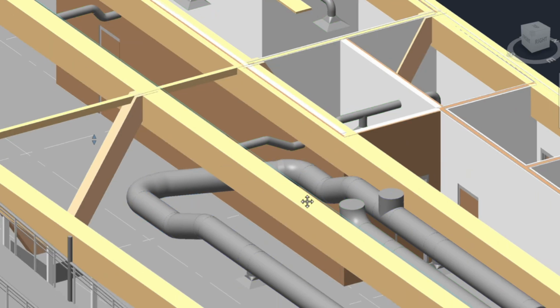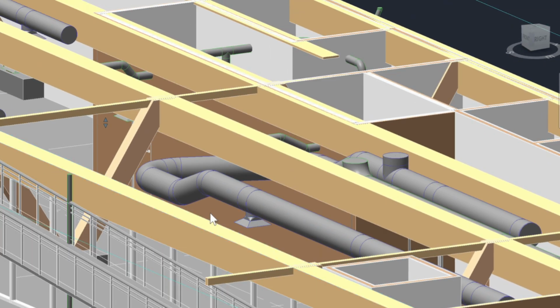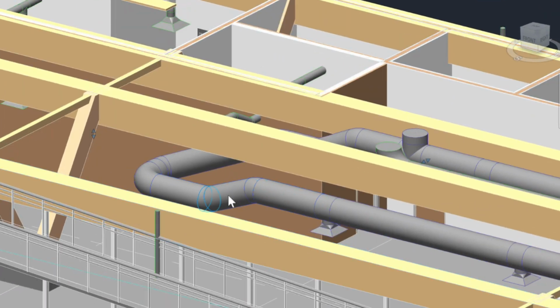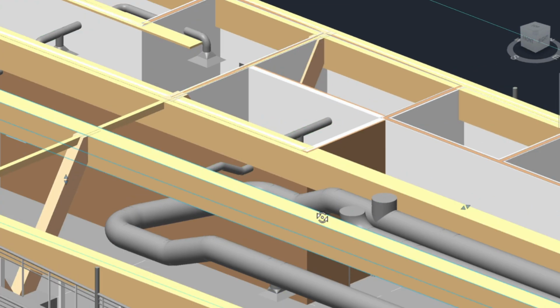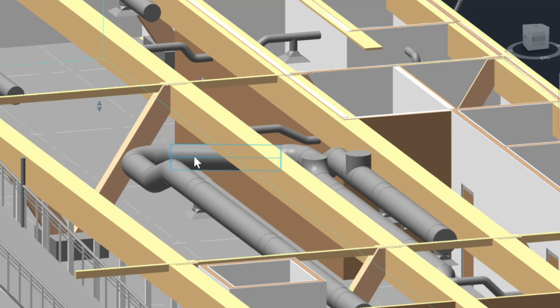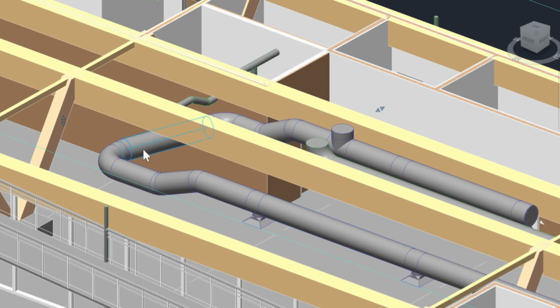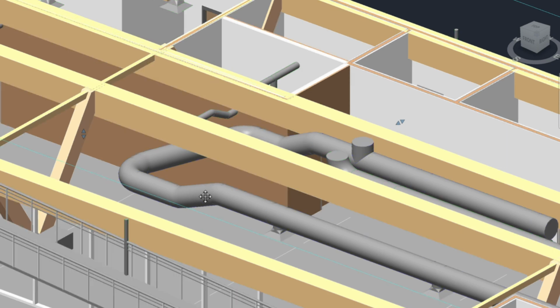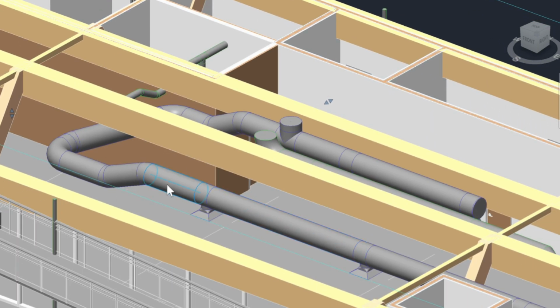We needed to go through the beam, so we made this sort of route that the duct could take in order to have — here you can see it clearly — it's under the beam. So maybe we have some problems with the 2.5 meters that we need, but it solves the problem. Maybe we could make an oval duct here, wider than its height, in order to get the free height, but this is the solution we came up with.